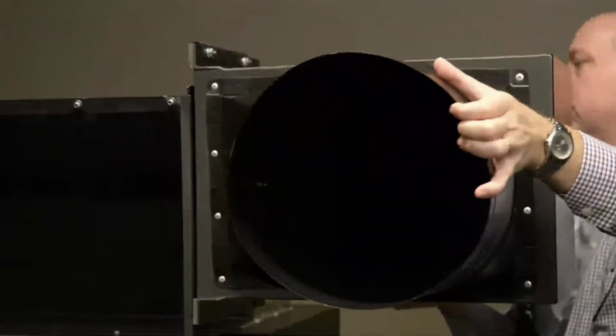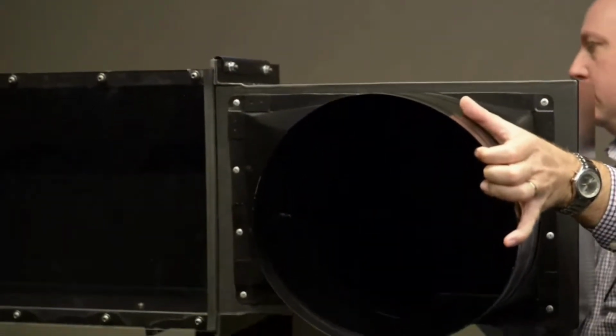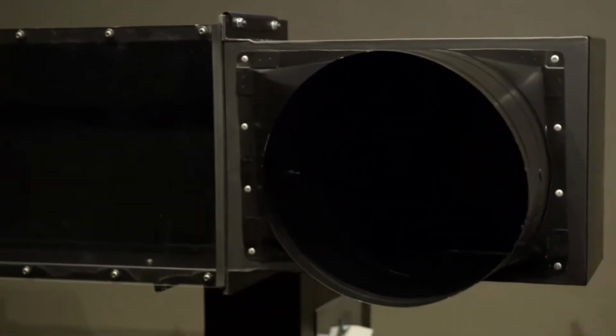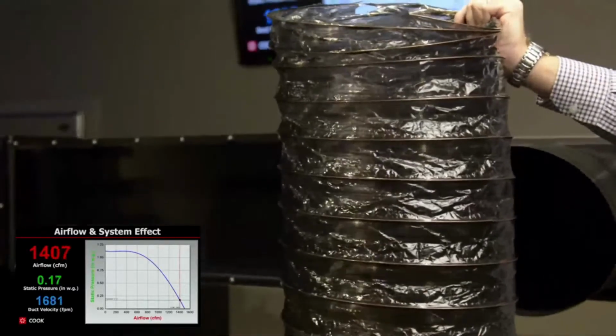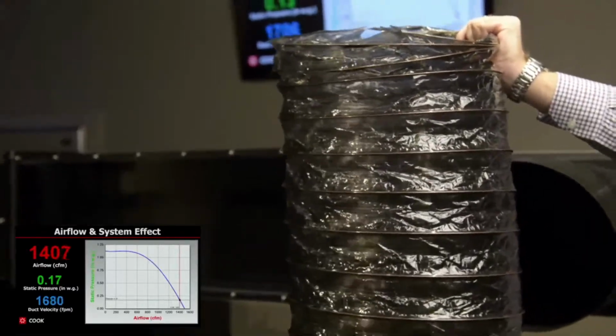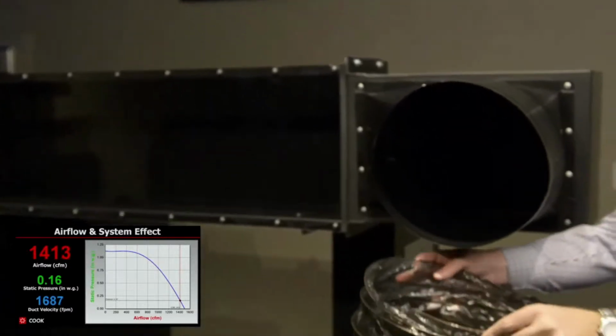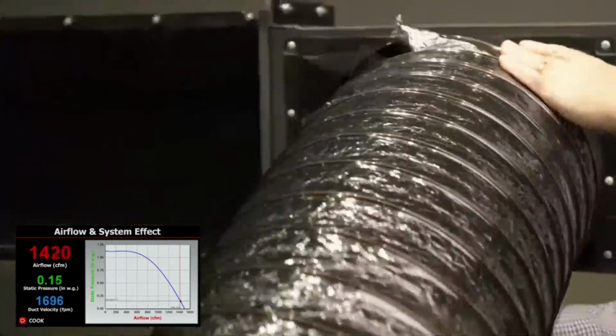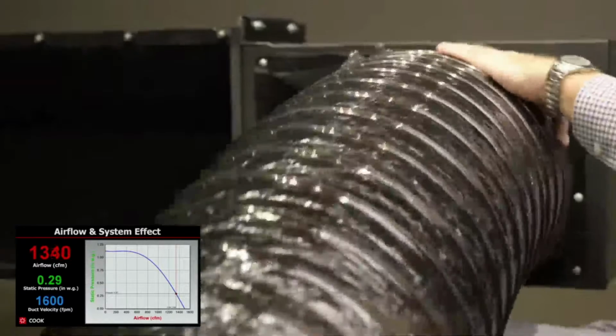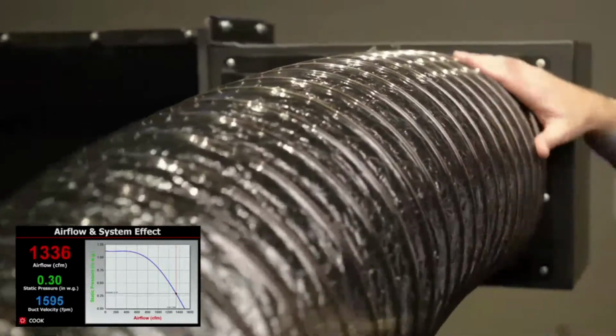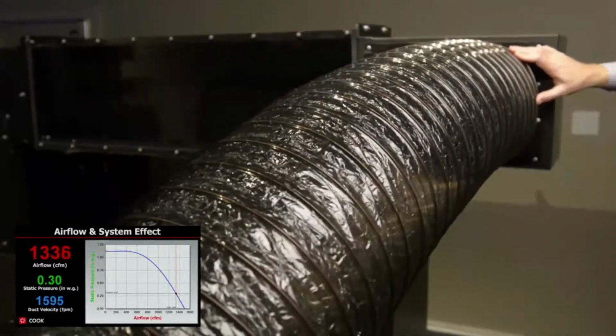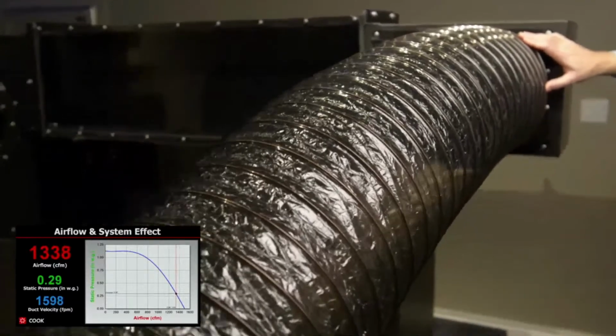A common fitting in duct systems is a high-efficiency takeoff. This is often used to attach a round flex duct to a rectangular duct. The pressure loss of the fitting itself is seen to be a 0.15. When we add a typical 5-foot length of flex duct, however, the pressure loss increases to 0.30, double the loss of the fitting alone. We can see that the flex is straight, which is rarely the case.